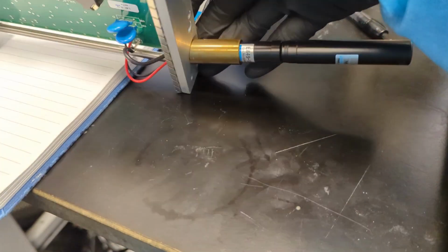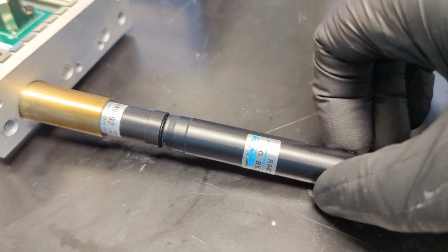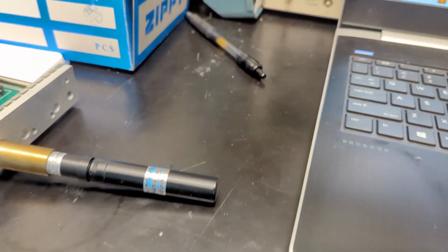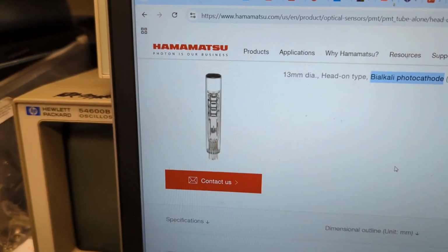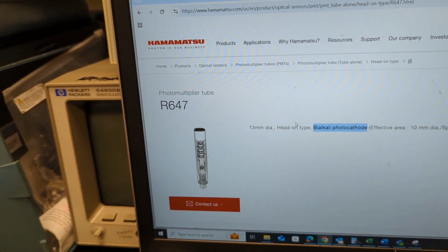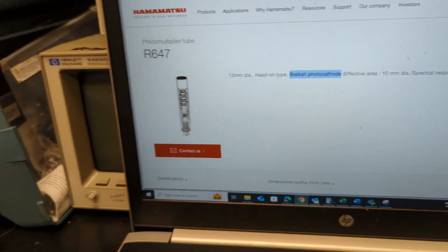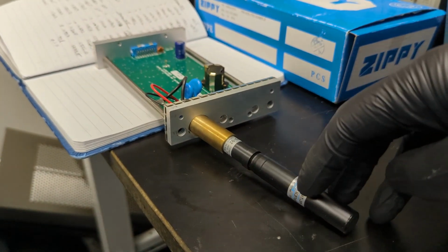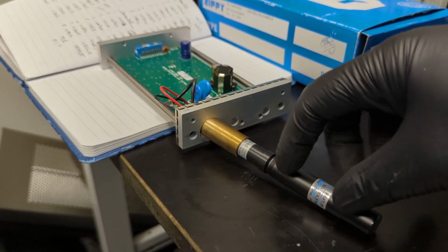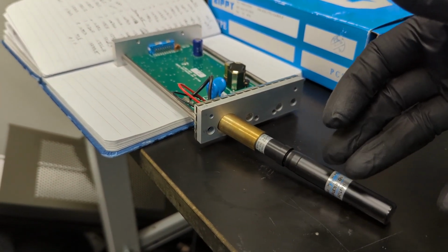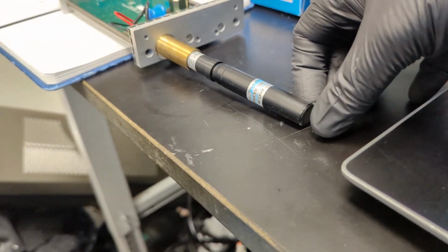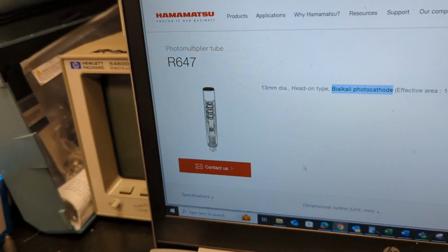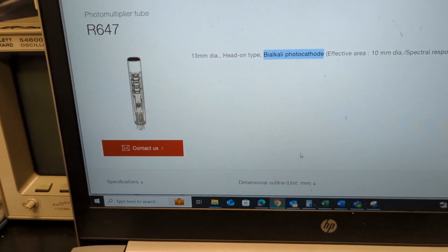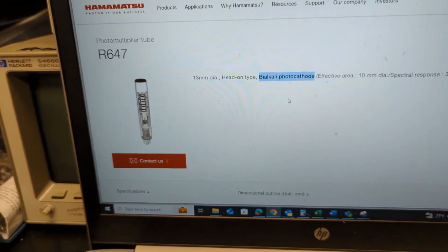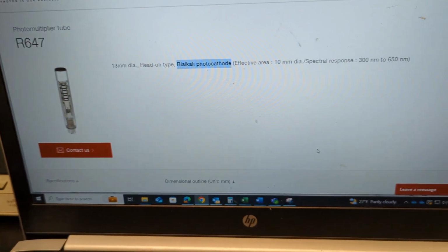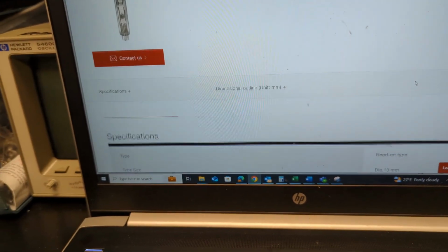All right, so this is a Hamamatsu R647. I see Hamamatsu PMTs in a lot of our instrumentation, and I'm actually on their website right now. This is it, the R647 photomultiplier tube, head-on type, which means that sometimes you'll see these tubes where the light is going to be read from the side of it. This is head-on, so it's being read from here. That's where the photocathode is. And speaking of the photocathode, this is a bi-alkali photocathode. I believe it is potassium and rubidium, and gives you the spectral response, and it gives you some specs here.